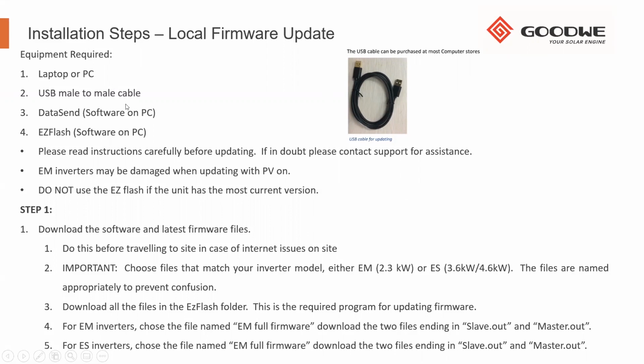So you do need a laptop or PC, a USB male-to-male cable, the software, DataSend, and EZFlash, and of course the instructions to be able to do it correctly. With the older EM inverters, if they have quite a very old firmware on them, you must just make sure that there is no PV on when you update these inverters, because it can damage the inverter. And if the inverter already has the latest firmware on it, it's not advised just to reflash it with the same firmware over again.